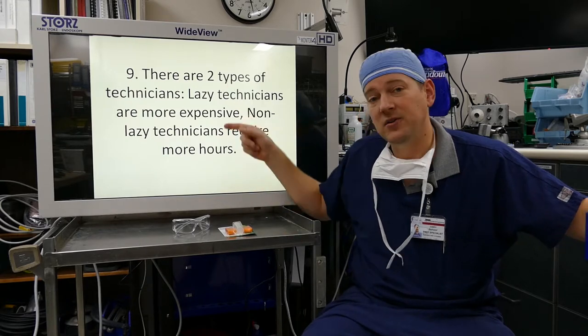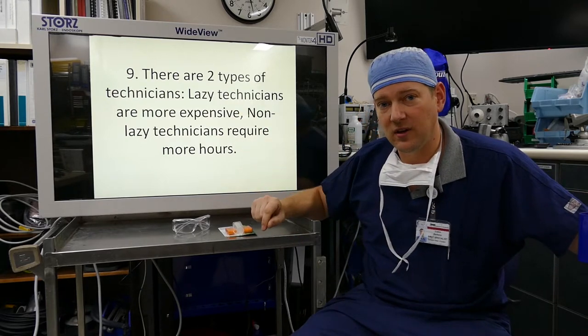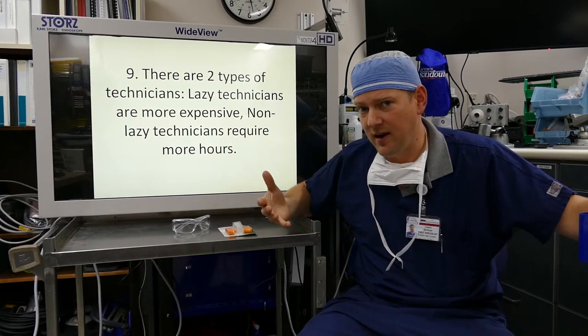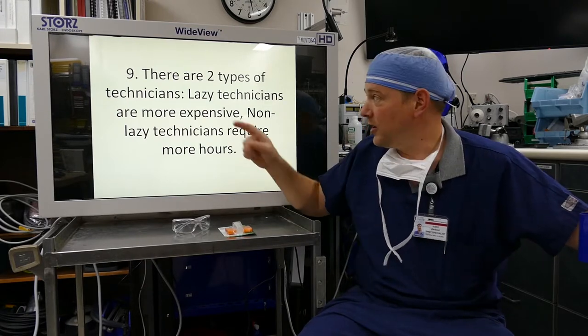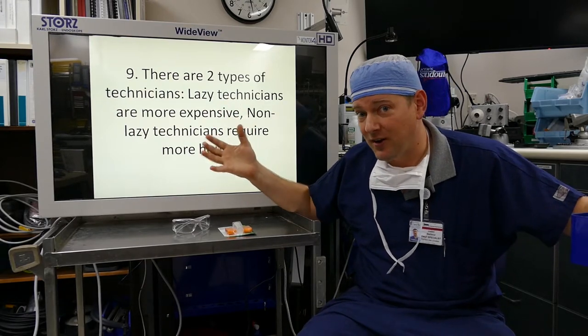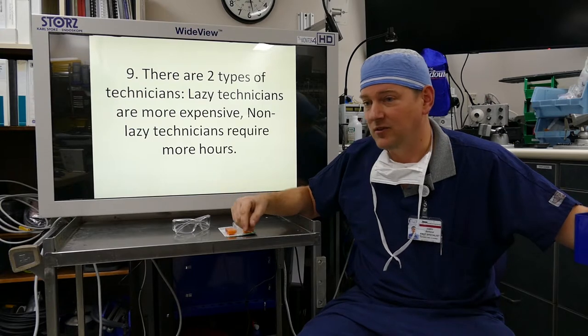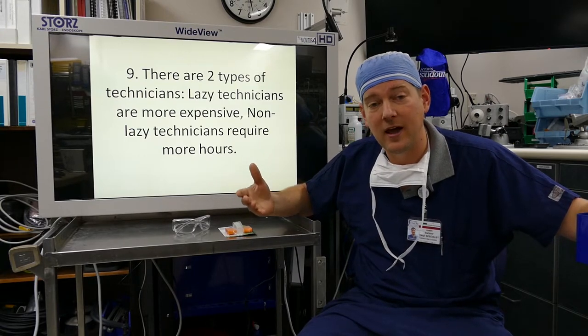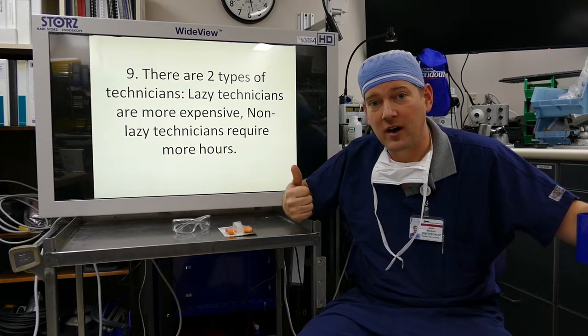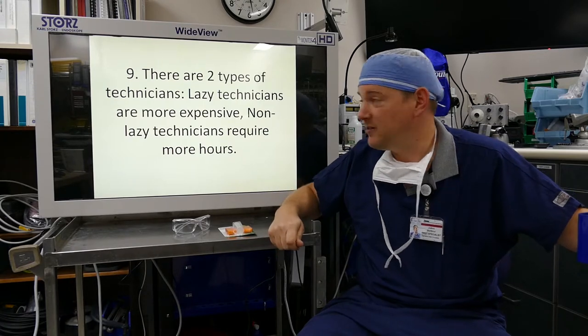Now this is a balancing act. Sometimes you have to ship things back to the manufacturer because you don't have time to deal with it, or because of the risk — when you open something up, you own it. Sometimes it's a high risk, talk about balloon pumps or something like that. If you're not certified to be working on them, then you should be shipping them back to the manufacturer.